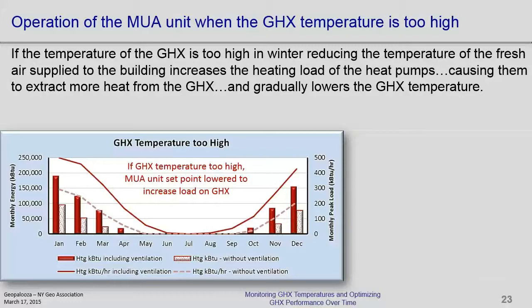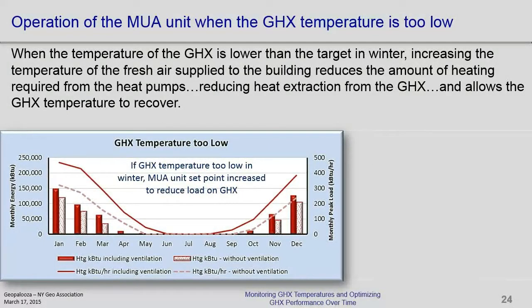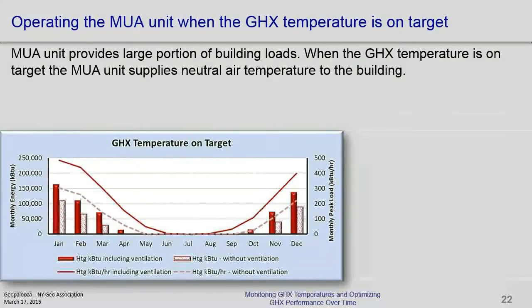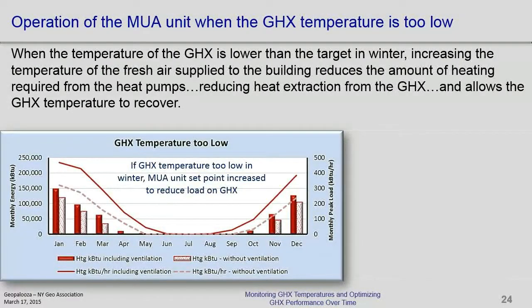If the temperature is too low in January, then he'll bump up the temperature a couple of degrees so that the heat pumps don't have to work quite as hard and won't extract quite as much energy from the ground. So you can control that to some extent. And since the makeup air is a fairly significant piece of the energy loads of a building, you've got a fair bit of control on that.